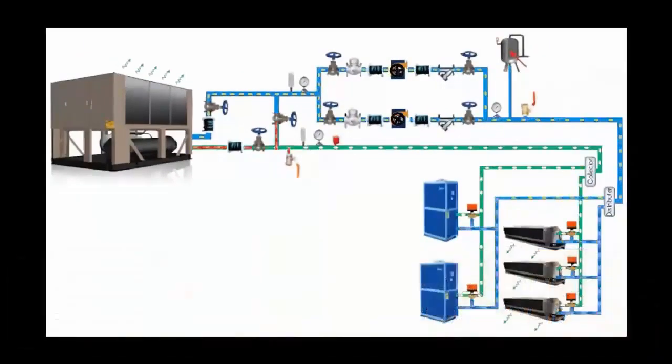3. The water switch is used to ensure the presence of liquid flow in the evaporator before turning on the chiller. If the switch is not activated, the power on of the equipment is prevented or it stops.